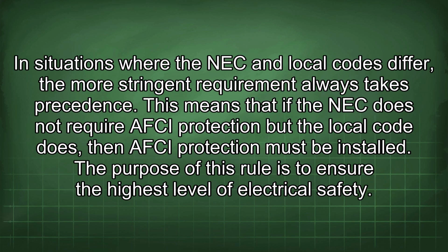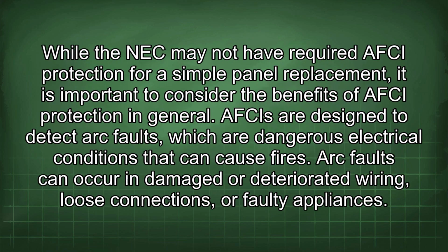In situations where the NEC and local codes differ, the more stringent requirement always takes precedence. This means that if the NEC does not require AFCI protection, but the local code does, then AFCI protection must be installed. The purpose of this rule is to ensure the highest level of electrical safety. While the NEC may not have required AFCI protection for a simple panel replacement, it is important to consider the benefits of AFCI protection in general.